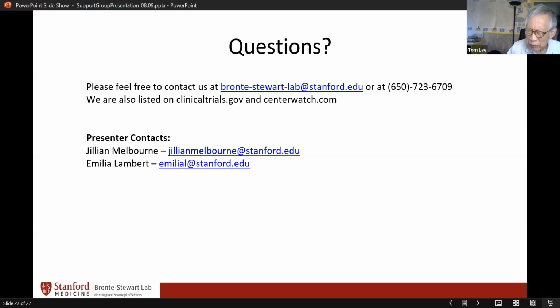Are you allowed for neurochemical recovery after intense stimulation? One thing that I think might help to explain: when we're doing our first day of testing, we have what we call calibration to make sure that we're finding stimulation intensities that are safe and tolerable for you specifically. And that might look different for each person, and on each side of the brain, it could look different. So we're looking for the lowest stimulation intensity where you see a resolution of symptoms. You're not at something that's subclinical. So say, for example, if you were at 50% of your clinical stimulation, you might not experience the same benefits for tremor reduction. So we want to make sure that we're above that threshold so that you're not uncomfortable.